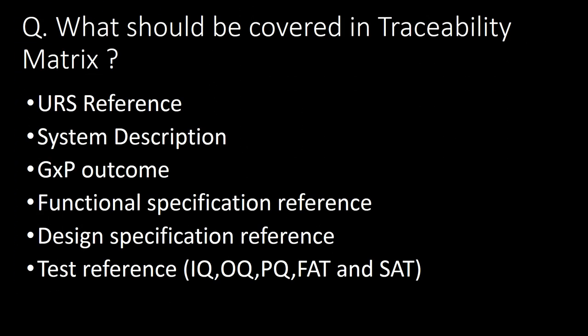What should be covered in a traceability matrix? The traceability matrix should cover URS reference, system description, GxP outcome, functional specification reference, design specification reference, and test references including IQ, OQ, PQ, FAT, and SAT.